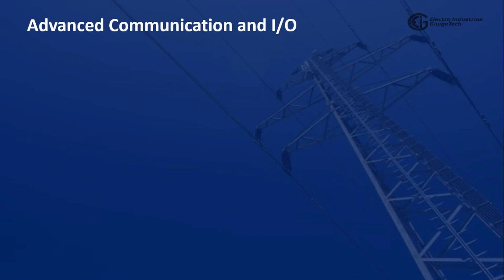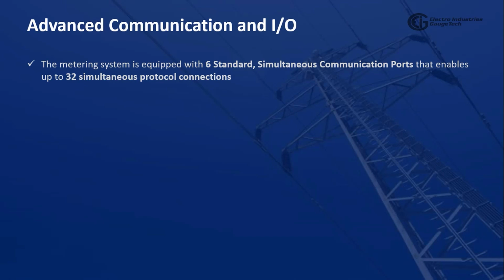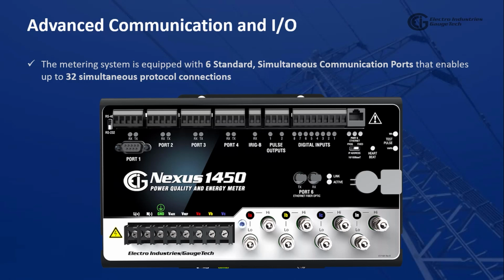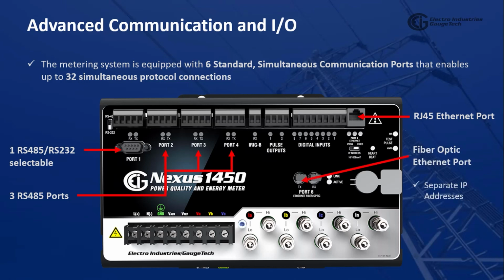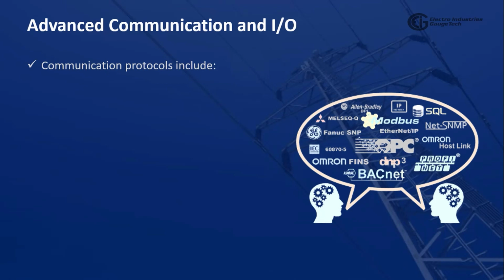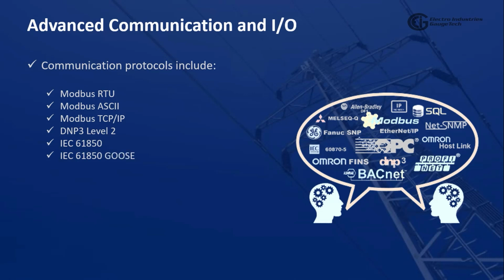The next defining feature of Nexus 1450 meter is the advanced communication and I/O. The metering system is equipped with 6 standard, simultaneous communication ports that enable up to 32 simultaneous protocol connections. It has 4 independent serial ports, 3 RS485 and 1 RS485/RS232 selectable. 2 independent Ethernet ports, RJ45 and fiber optic, with separate IP addresses, advanced port control, encrypted email on alarm, web server, and DHCP. Communication protocols include Modbus RTU, Modbus ASCII, Modbus TCP/IP, DNP3 Level 2, IEC 61850, IEC 61850 GOOSE, SMTP, SNTP. RS485 port supports RTU master.